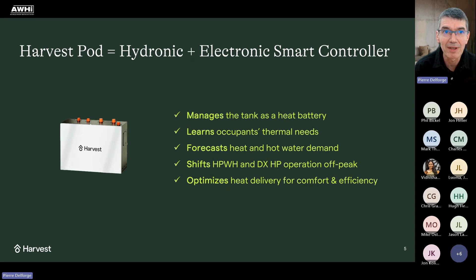So, key differences with conventional air-to-water heat pumps. The first one is operating temperatures. By using a Sanco 2 heat pump, which is very good at heating water in a single pass to about 150 degrees, we are able to operate it at a high temperature without a significant efficiency penalty. And the proof is here in the annual operating efficiency that we get. We get about 3.8 average annual operating efficiency for the Sanco 2.